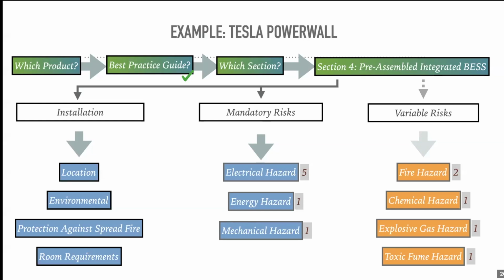So you have to check that they're compliant with the best practice guide. How do you do that? You need a manufacturer's declaration, right? The manufacturer should provide you with a declaration that they comply with the best practice guide. So that means you go into section 4, and section 4 has mandatory risks for installation, the blue ones: electrical, energy and mechanical. Then they have some variable risks which are based on things like what type of chemistry it is and where it's installed.